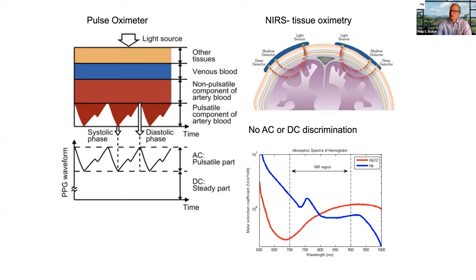Light is modulated by the pulsatile blood as it moves through the finger. There's a static component and a variable component. The variable component is called the AC component. At 660 and 940 nanometers, there's differential absorption of oxy and deoxy blood, as shown in the diagram. So this method depends on pulsatility and adequate light signals.